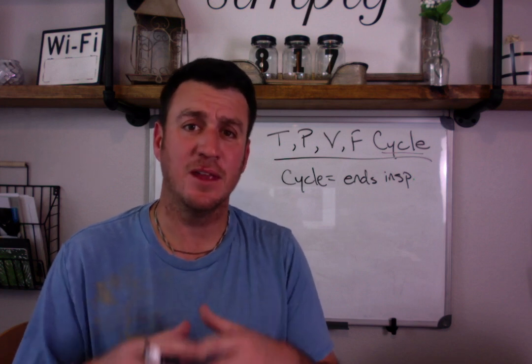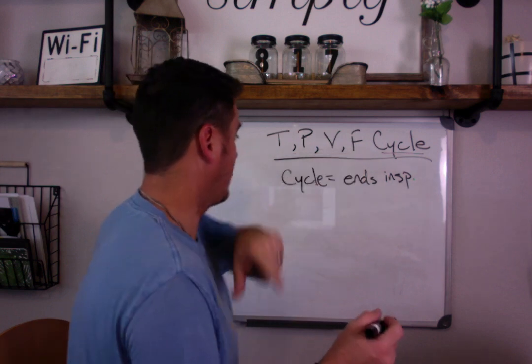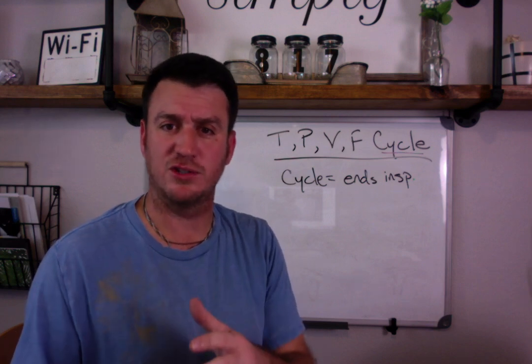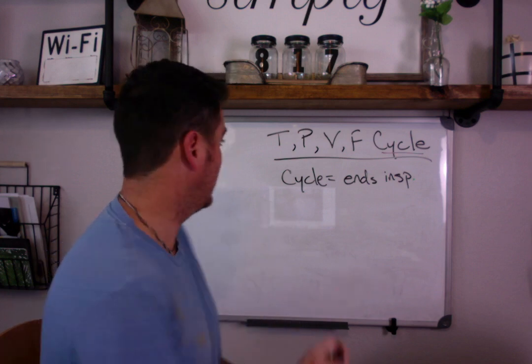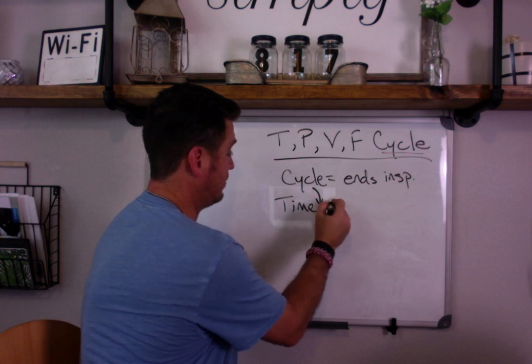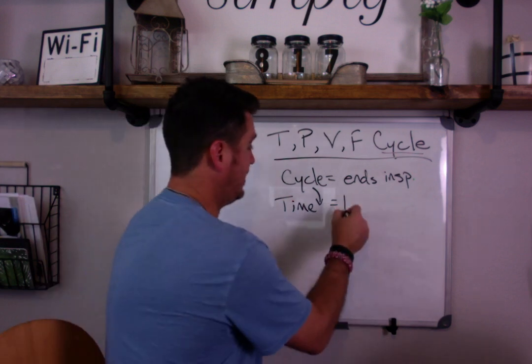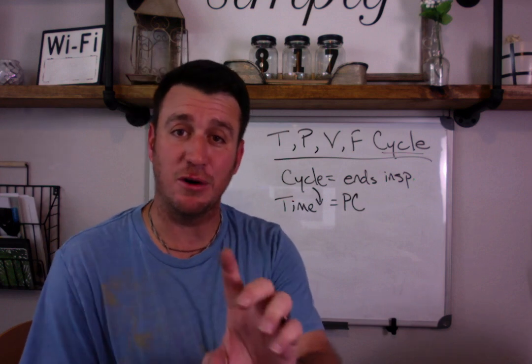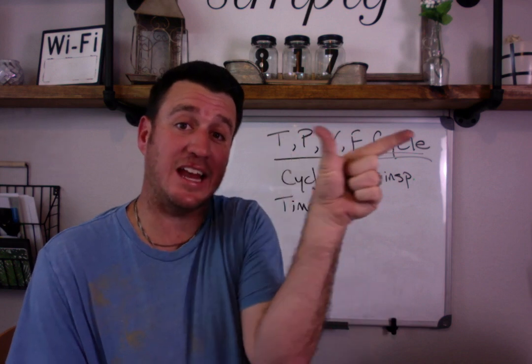When you hear on a test, board exams, or you're just looking at this stuff and you don't know if it's time cycled, pressure cycled, or volume cycled, you need to ask yourself: what is cycle? Cycle is the mechanism that ends inspiration — what tells the ventilator or the machine to stop the inspiratory phase, close the inspiratory valve, and open the expiratory valve. Now, we're going to go in this order: time, pressure, volume, flow. The first one is time cycle.